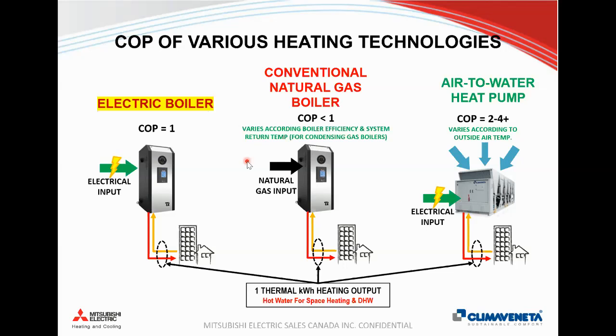So just to compare energy and carbon emissions of different systems, if we look at hydronic systems, if we want to keep doing hydronic systems, but we want to decarbonize them, essentially our only other choices are electric boilers, which always have a COP of 1, or an air-to-water heat pump that has a COP anywhere from 2 to 4 or more. The air-to-water heat pump, though, is influenced by ambient temperature, where the electric boiler is not. But if we compare this to a natural gas boiler, our COP is always less than 1.